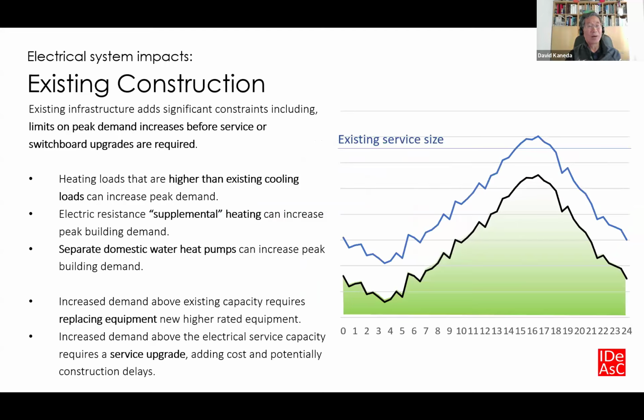Where it gets a little more complicated is with existing construction. The first thing, of course, is we're constrained by the size of the service and the size of the equipment that already exists. If that number goes up, there's potential to exceed the size of the service and/or exceed the size of the panels serving the AC unit that you want to use to feed the heat pump unit.